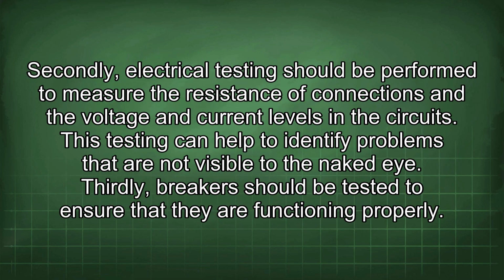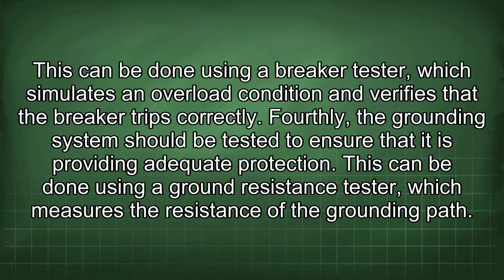Secondly, electrical testing should be performed to measure the resistance of connections and the voltage and current levels in the circuits. This testing can help to identify problems that are not visible to the naked eye. Thirdly, breakers should be tested to ensure that they are functioning properly. This can be done using a breaker tester, which simulates an overload condition and verifies that the breaker trips correctly. Fourthly, the grounding system should be tested to ensure that it is providing adequate protection. This can be done using a ground resistance tester, which measures the resistance of the grounding path.